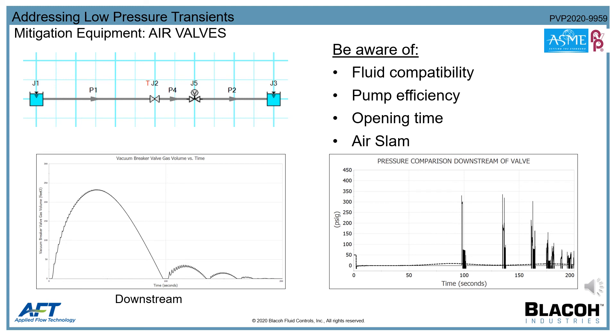The last challenge to consider is a phenomenon called air slam. This occurs when the air valve is closing and air is leaving the system too quickly, causing the valve to slam shut when the fluid columns come back together — creating a secondary high pressure transient event. One method of preventing this is to select a multi-stage air valve that controls the air release via an orifice.